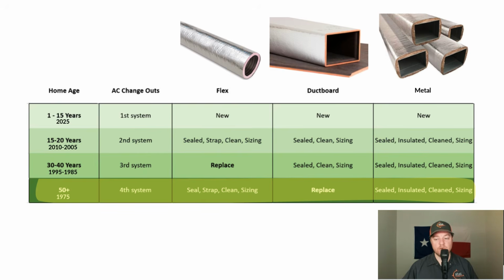Now, when it comes to metal ductwork, you got to do the same thing as last time. Make sure everything's sealed, insulated, cleaned, and sized right. So I want to pause right here because whenever I'm talking about ductwork lasting this long, you also have to be following all the best practices. And probably the most important one is the sizing of the ductwork, because whenever we talk about ductwork lasting this long, we typically run into some issues.